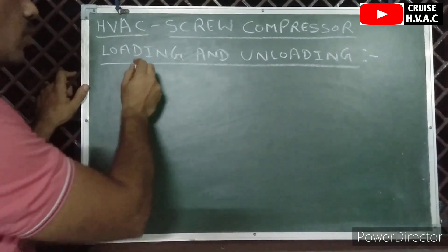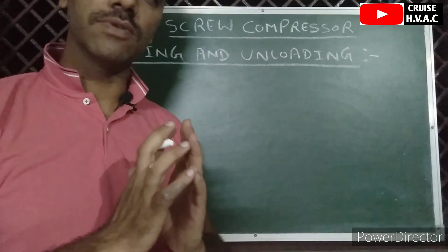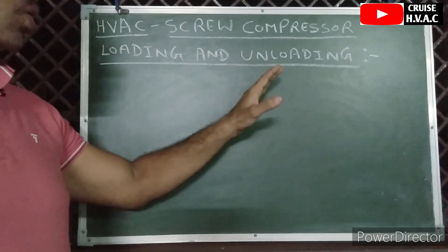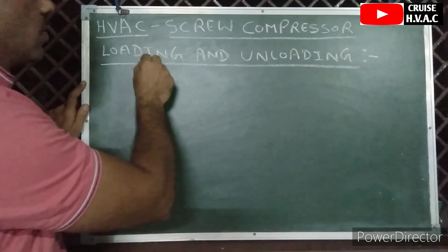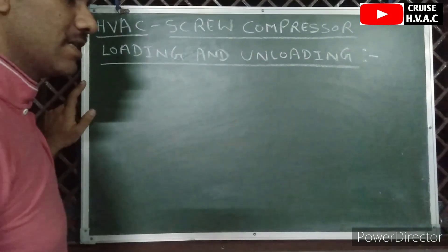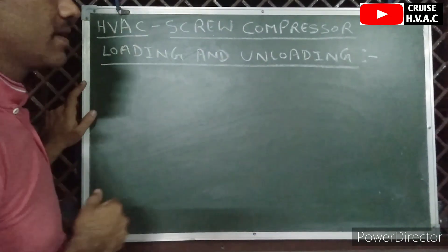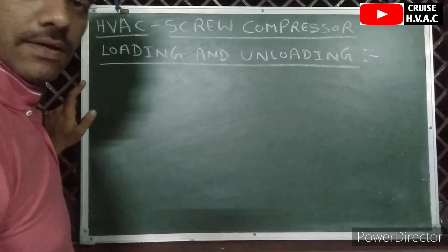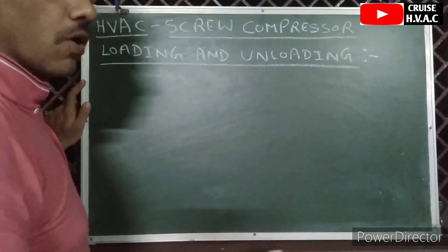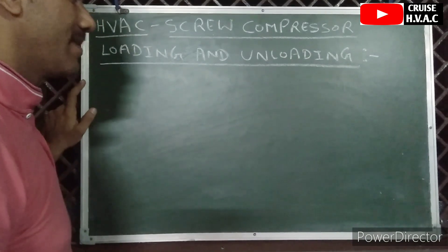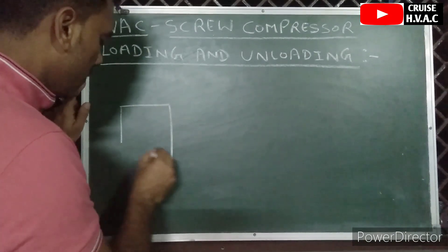Today our topic is the screw compressor in HVAC — specifically what loading and unloading means. When the compressor is on high load, how does the mechanism inside work? And when the compressor is on low load, how does the mechanism work? For the screw compressor especially, there is one device called the sliding valve. This sliding valve controls the flow of refrigerant in the screw compressor according to loading and unloading. The key component in this mechanism is the four-way solenoid valve.